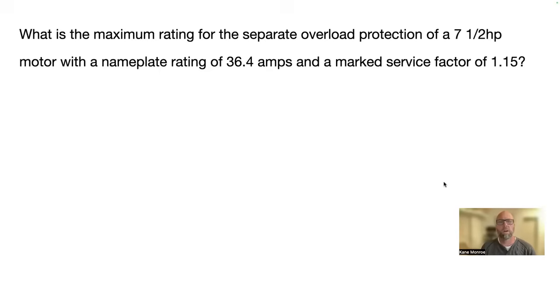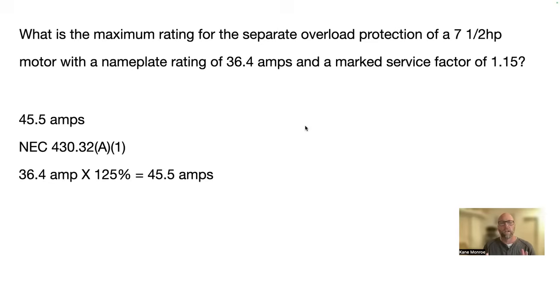Guys, remember, your overloads are not your overcurrent protection. Your overloads are your heaters. Your overloads are always your heaters and you'll always use your 36.4. There is a factor because they're telling you 1.15. So what we do is we go to NEC 430.32 A1 and look in that chart and it says if there's a service factor marked on the nameplate of 1.15 or greater, you multiply your FLA by 1.25 or 125%. So 36.4 amps times 125% is 45.5 amps. So your answer would be 45.5 amps.